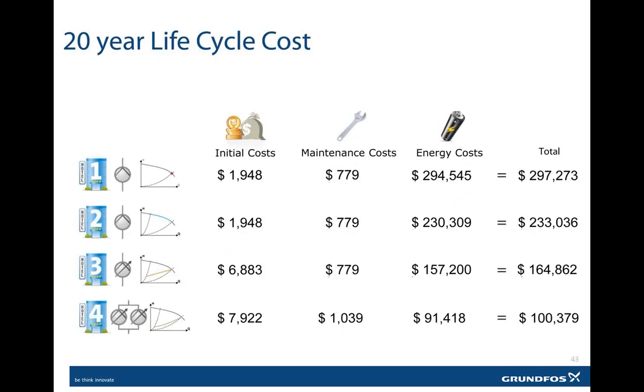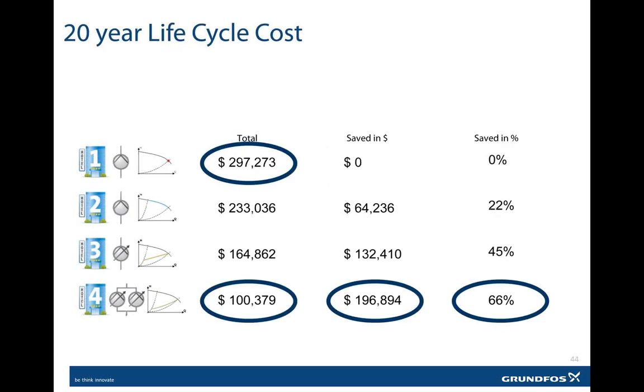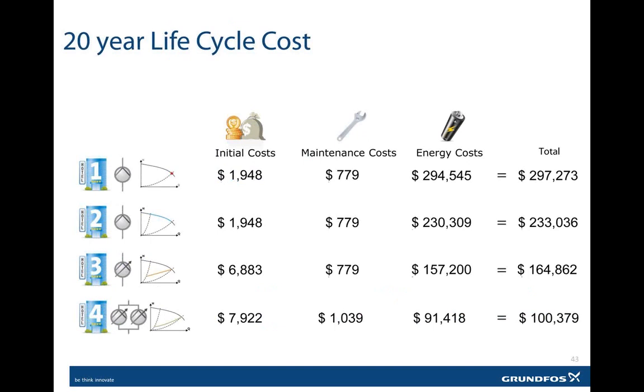So if we look at these from a life cycle cost analysis for the 4 examples over a 20-year period, and we'll look at the product, which again in a good system is the life expectancy for the system, we can see that the first single pump operating at a constant speed, constant flow, its initial cost is $1,948. Our maintenance costs are $779 for a total energy cost over the 20-year period of $294,545, which gives us a total cost for the system, or a total life cycle cost for this application, of $297,273.